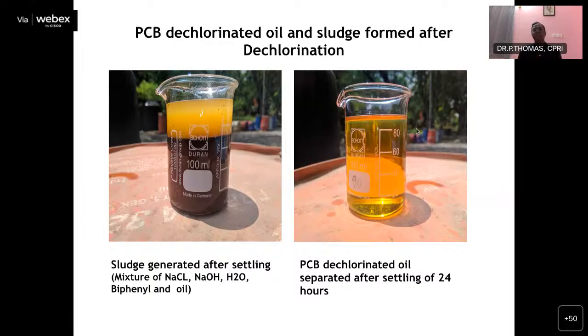Looking at the economics, suppose you have PCB contaminated oil and you remove all the PCBs, the oil remains and almost 20% will be sludge. So from 100%, sludge is around 20%, and you get only 80% yield from the treatment. That 80%, or whatever the yield, can be further treated.